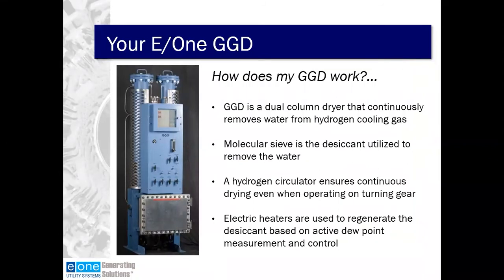So how does your gas dryer work? The E/One generator gas dryer is a dual column dryer that continuously removes water from the hydrogen cooling gas. Having 2 columns enables the dryer to be drying on one column, while the second column is either in regeneration mode or available to be brought online when the drying column reaches its saturation point. We use a molecular sieve as the desiccant to remove the water vapor from the hydrogen gas. The GGD has a hydrogen circulator, and this ensures continuous drying even when we're operating on turning gear.